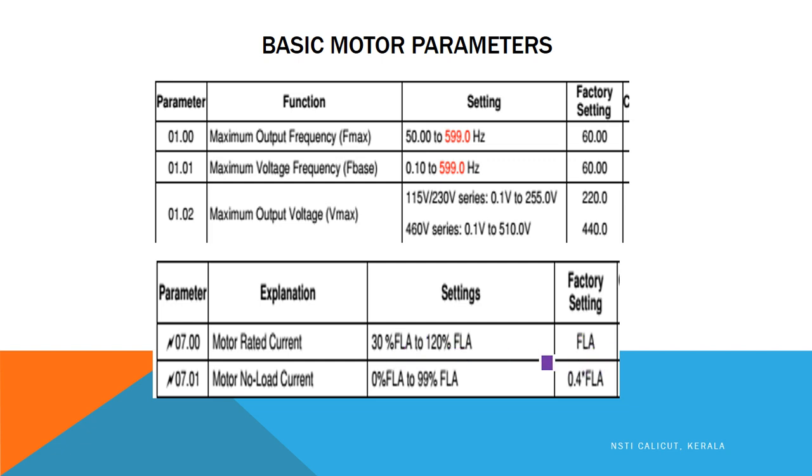like that. But it is better to go for 1.3 only, because when the motor is taking higher current, it will be overheated. There should be sufficient protection to prevent that. So the motor current is being specified by a parameter in the VFD. So what does the VFD do? If the motor current exceeds that, we can make additional protections. So this parameter has to be set by the user before commissioning the instrument.